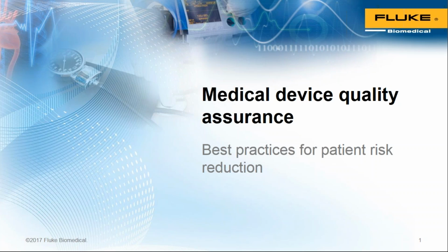Similarly, in a Class IP device, again for electrical safety purposes, IP meaning internal power, like a battery, if the device is intended to be used on its internal battery, then you will not have a ground source to do that earth bond test upon. So it's required on all Class 1, electrical safety Class 1 devices for sure, and it is a test that needs to be run also by facilities in evaluating the power distribution system of the hospital to make sure that all grounds are indeed ground, connected to ground and nowhere else, no matter what else we're doing.